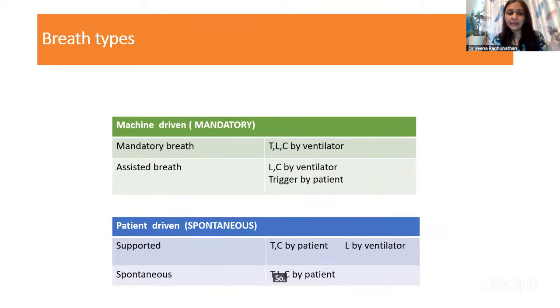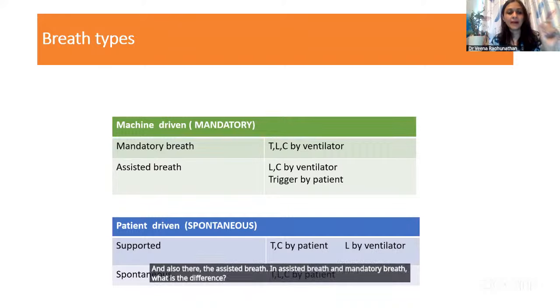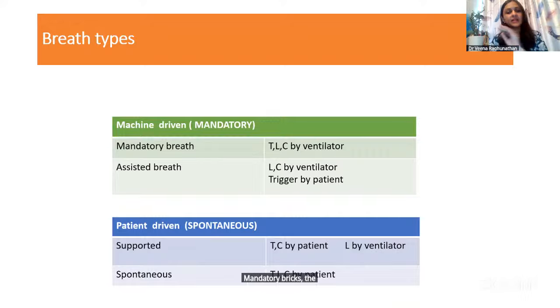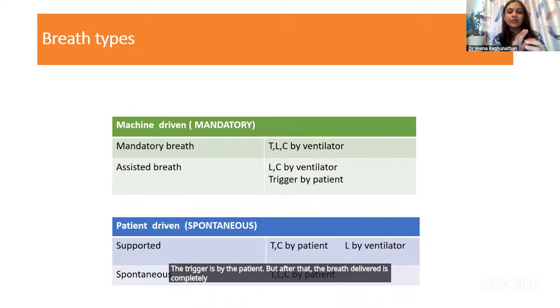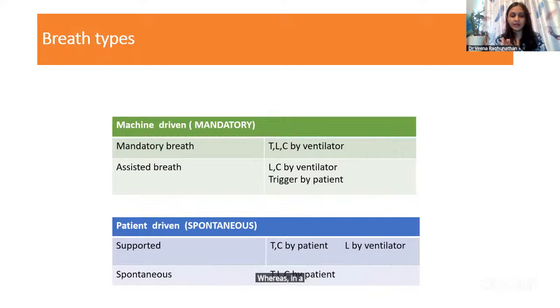So a mandatory breath is a machine-driven breath, and then there is also the assisted breath. What is the difference between assisted breath and mandatory breath? In a mandatory breath, the trigger, limit, and cycle are all by the ventilator. In an assisted breath, the trigger is by the patient, but after that, the breath delivered is completely taken over by the ventilator, so the limit and the cycling happen by the ventilator. Whereas in a supported breath, the trigger and cycling are by the patient, but the limit is by the ventilator.